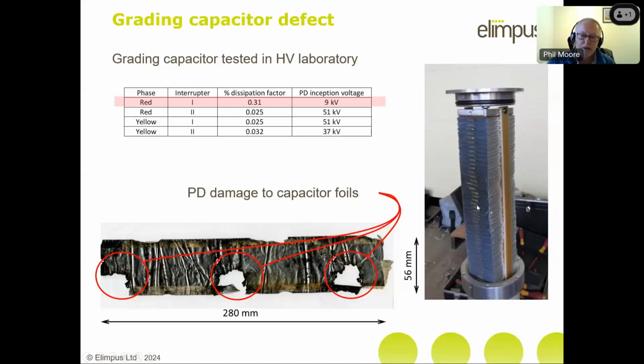And this was just basically sparking every time that circuit breaker had operated. You were getting sparking inside this grading capacitor, again caused by this very high voltage due to the transient that shunt reactors produce. And that had sparked and eroded away this to the point where it was pretty close to actually breaking down. It wouldn't have taken too many more operations, and that would have completely shorted it, and then you'd have had a very big problem on your hands. And that was one of the big firsts that we got with this technique, and probably led to further work.